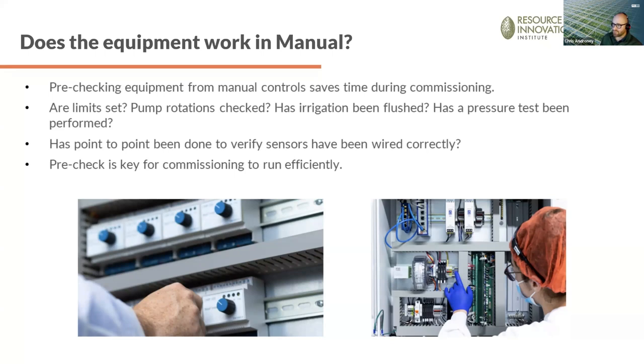Pump rotations - you want to make sure your pumps are pumping in the right direction. We also run into some funny situations with irrigation - has the irrigation been flushed? You sometimes find dirt, plastic shavings from installations, and we also find strange things like rags or all kinds of different stuff. So make sure the irrigation's been flushed ahead of time - that's very important. And also, has a pressure test been completed or performed?